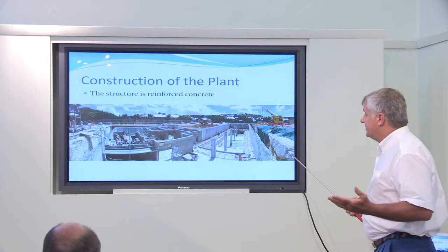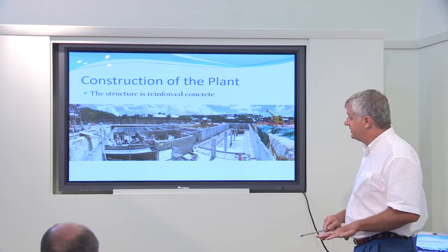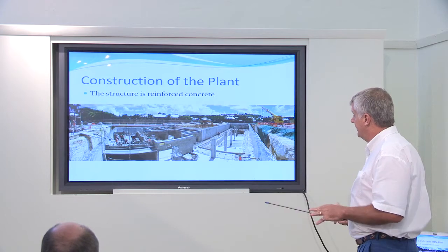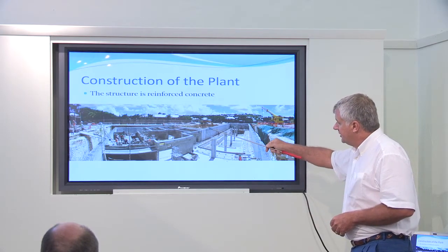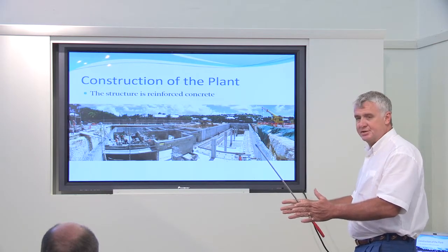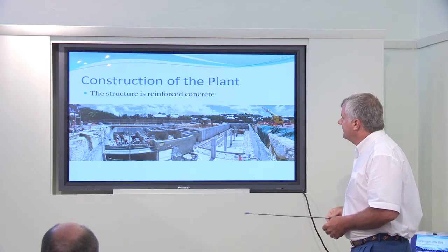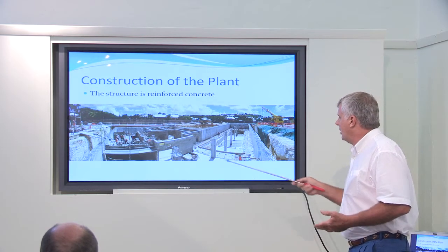The structure is reinforced concrete. There's just a large concrete box. It needs to be waterproof. It's under the ground, and obviously you don't want water getting into it. Quite a tall structure, about 21 or 22 feet. So you need thick walls, 16-inch thick walls on that. All of the other construction was pretty standard. There's some blockwork in it and so on.